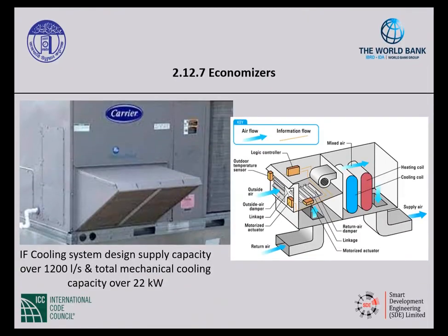All right, economizers. So we talked about this a little bit earlier when we talked about the requirements for using that outside air and what are ways that you can do that. Economizers is one of the most common ways that people use free cooling, what I call it, where instead of paying to run this system to cool the air, we're bringing in the air outside that's cooler than what we're trying to cool it to anyway. And so an economizer is one way of doing that.